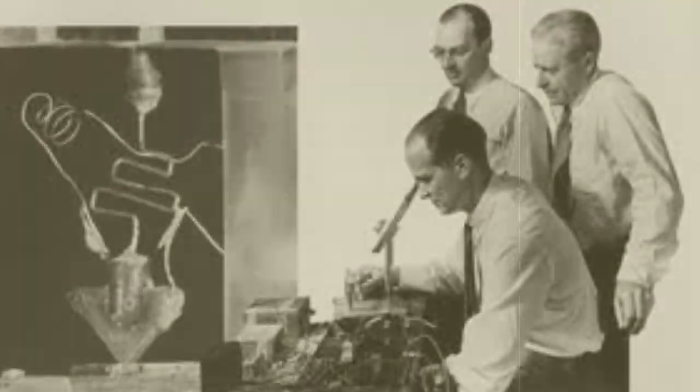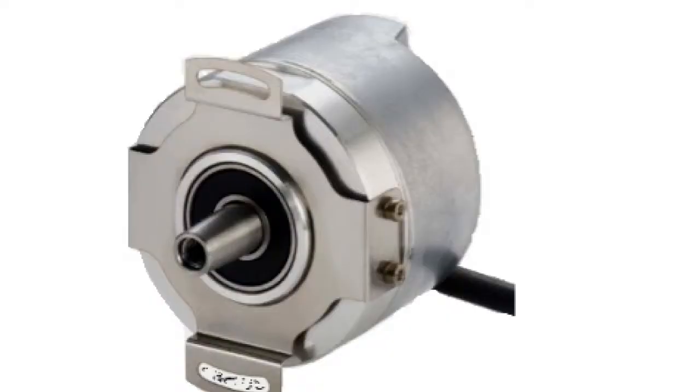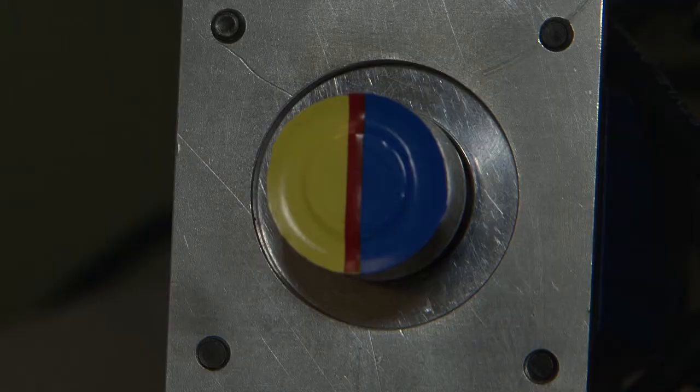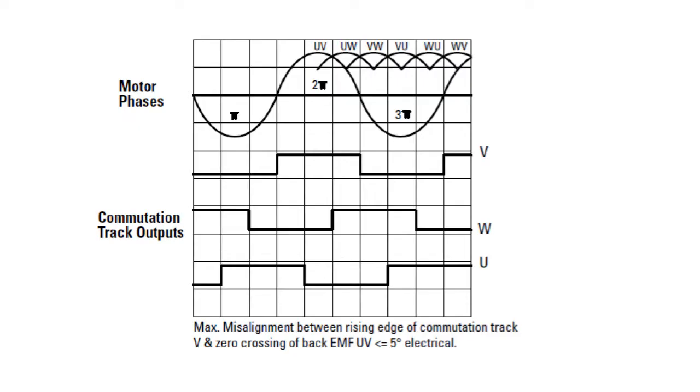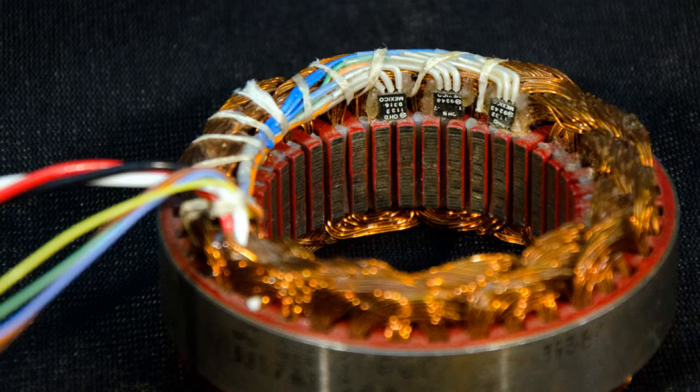In motion control, we will use Hall Effect devices in conjunction with other feedback types, such as TTL incremental encoders, to prevent having to find the rotor position through a technique called wake and shake, in which the motor makes a series of step-like moves. Inside the motor, the Hall Effect sensors are aligned with the motor's back EMF. Since the magnetic field passing through the windings is what produces the back EMF, the Halls will provide an output telling the drive when the magnets are aligned with the windings. This is only a coarse positioning of the rotor, used to prevent wake and shake.